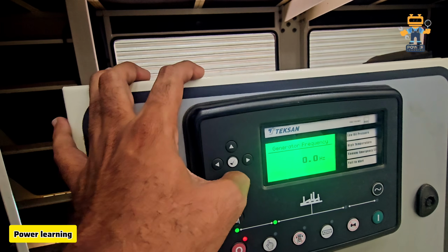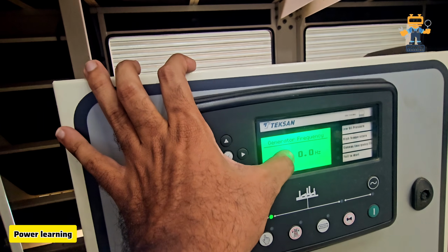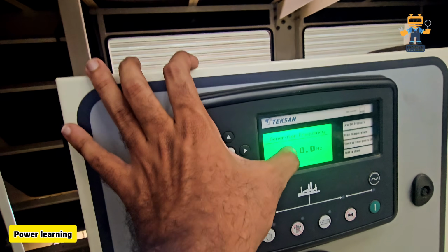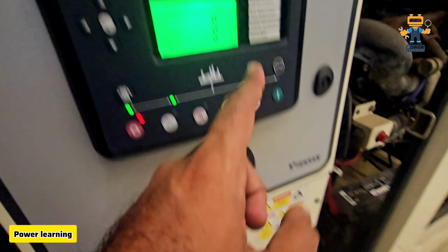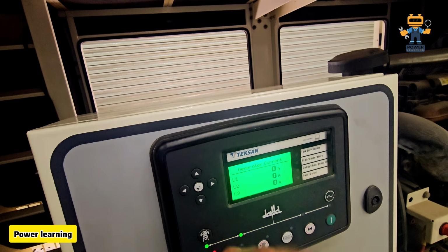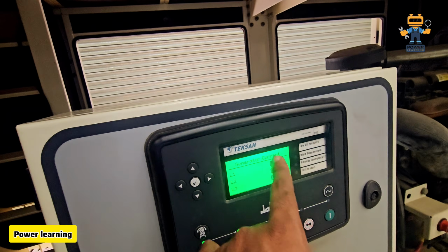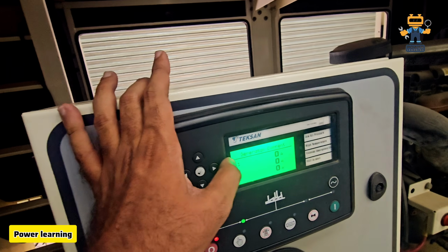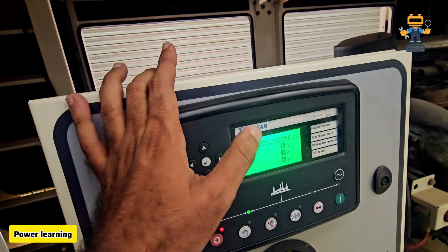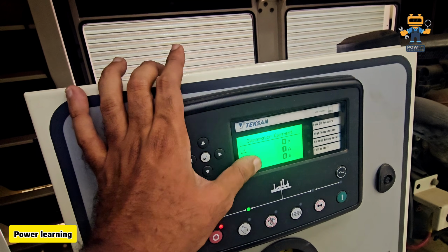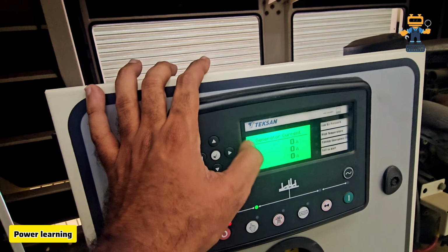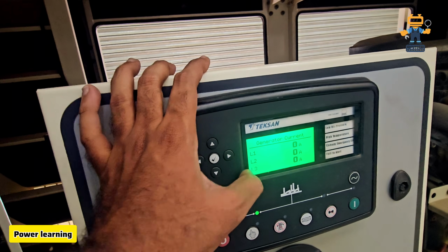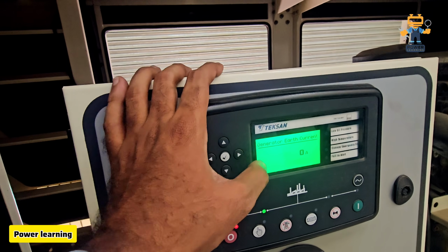Okay. But then here frequency 60 Hertz. Now we will run the generator and we will see. Here, whenever we have load on the customer side, it will show the ampere. But now, once we operate the generator, there is no load, so it will show 0. So this is load. Normally, if we go to any site where the customer already has a generator, we can check the load from here, how much of the generator they are using, what the size is, and what load they are now using.